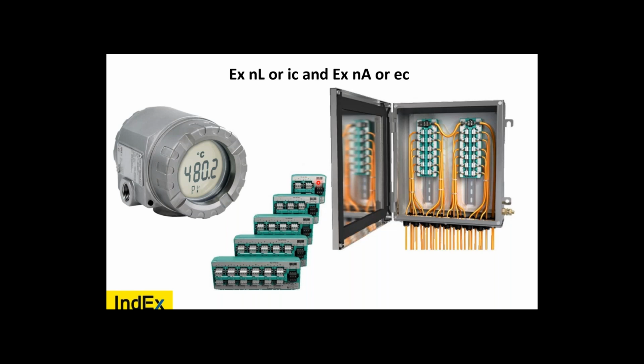If they're old, they would be EXIC if it's the newer standard. So it was NL and then it became IC. NL can't be out in open air, so you had to put it inside of a junction box. What was the zone 2 junction box available? NA. So the NL went inside the NA, which fed an NL circuit out to an NL instrument.